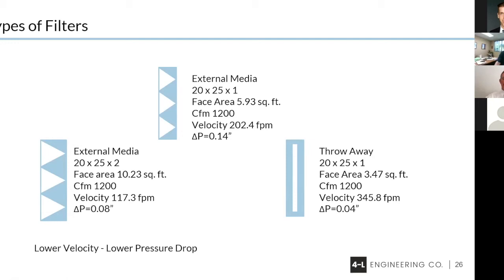Some of the things I can do to improve this problem is typically over there on the bottom right, I start with a standard 1-inch throwaway filter. It's vertically straight up and down. And it starts with a pressure drop of around 0.04. If I move to the center filter, here I change from a 1-inch vertical filter to what we call an extended media, which is a pleated type filter, which has pleats in it that move in and out. That provides us with an extended face area. And my face area on my lower right went from 3.47 square feet to a face area of 5.93 feet. And my pressure drop went to 0.14.